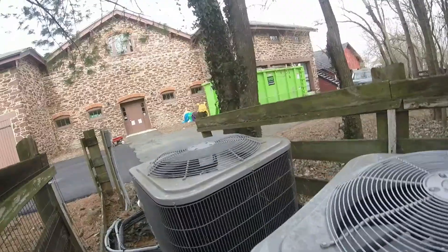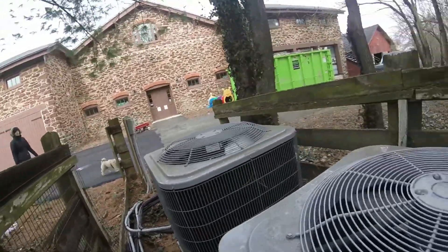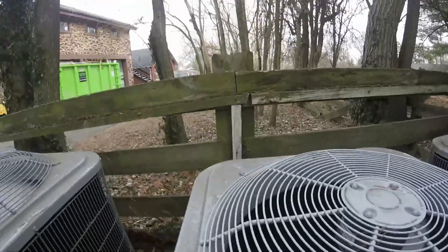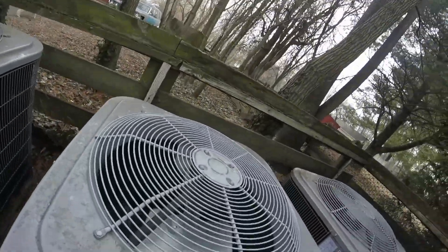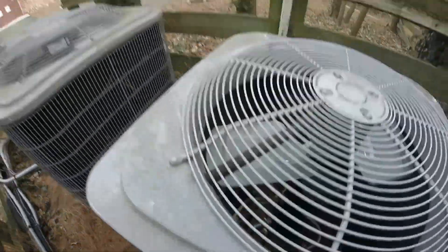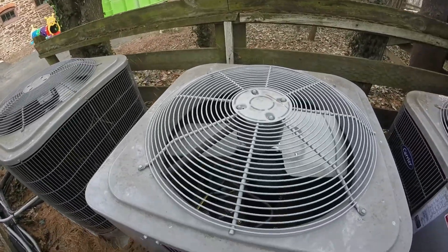Anyways, let's get out of here — I'm freezing. Are we done? Yeah, we're done. Let's sign off — oh wait, nevermind, because one just kicked into defrost. This one just did. This one just kicked into defrost. This is the same one I caught on November 6th — it was frosting and it was steaming. I don't know if this one's going to steam, but this one just kicked into defrost.